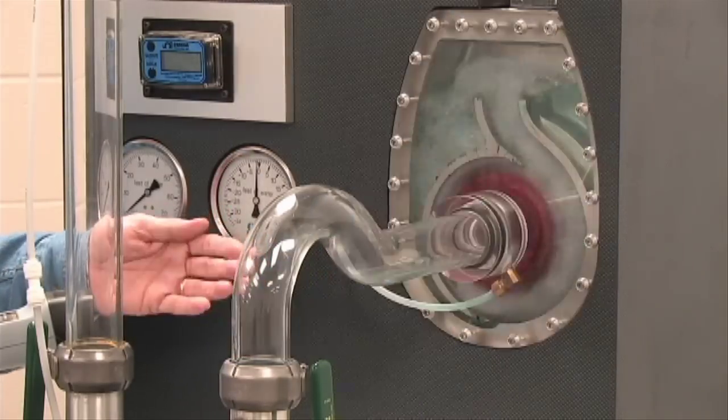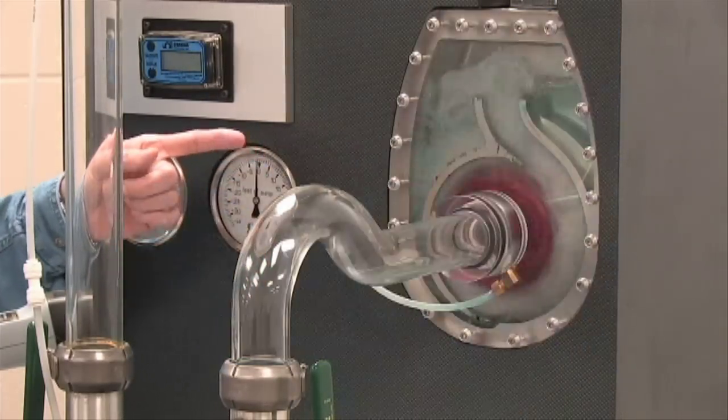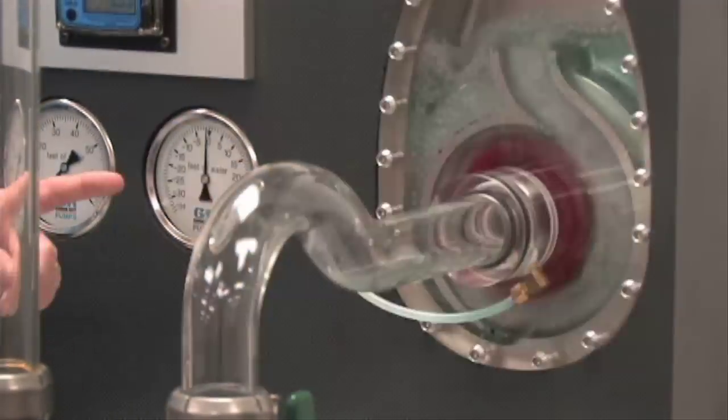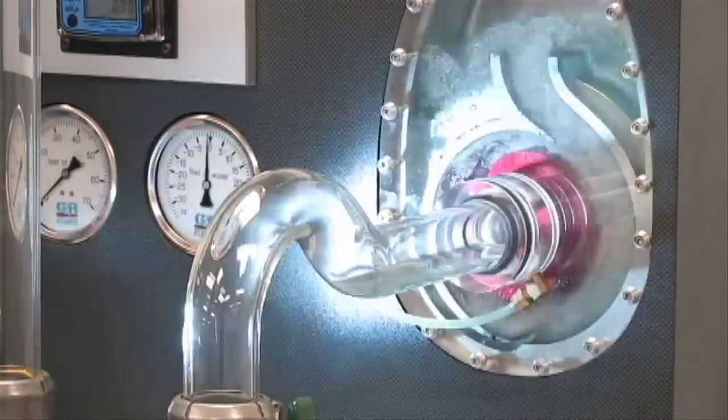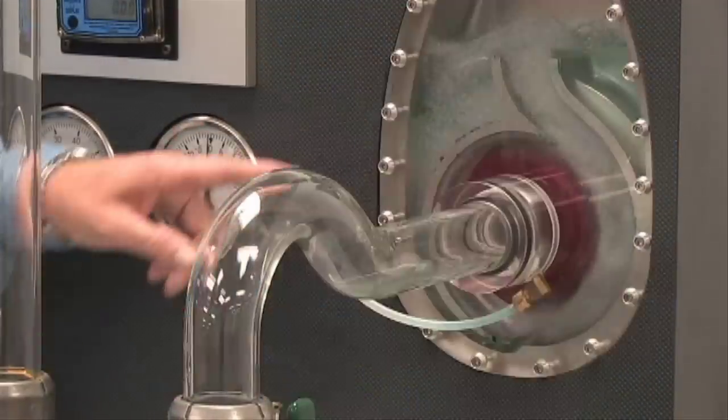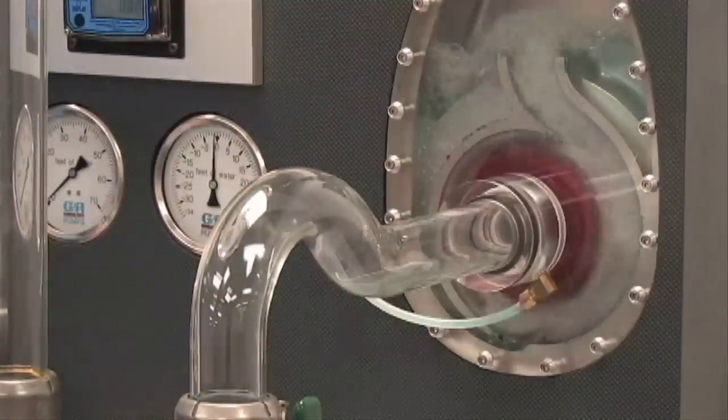After we fill the volute casing with water and we energize the pump, the impeller turns in a counter-clockwise rotation. The initial prime of the pump is slung through the volute scroll or the ever-increasing water channel into a pressure cavity or a discharge chamber inside the volute.